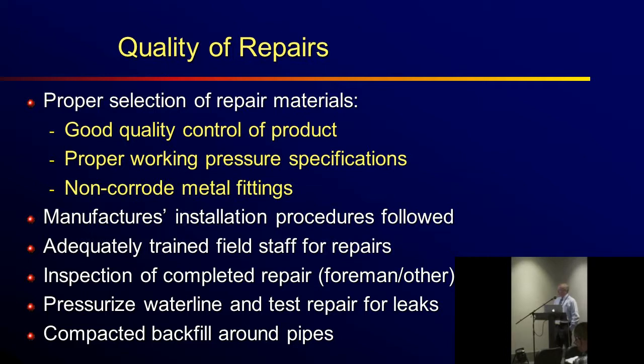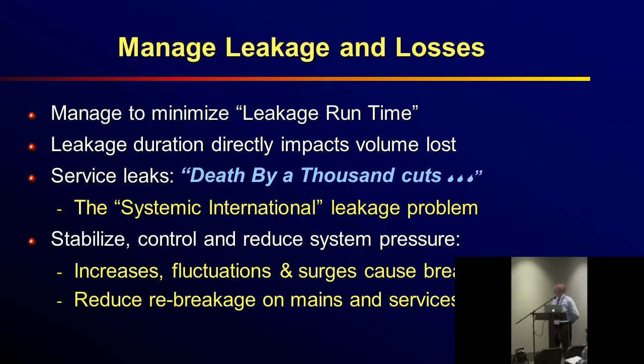An inspection of the completed repair, not just button it up and turn it off and walk away, but pressurize the systems, flush the systems, and ensure there's no additional leakage before final backfilling. And then there's final compaction at the end of the day. So again, coming back to managing leakage and losses is to manage reducing the leakage runtime. Again, leakage duration directly impacts the volume of water loss.